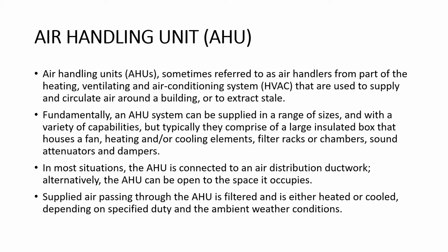So move on to air handling unit, AHU. Air handling units, sometimes referred to as air handlers, form part of the heating, ventilating, and air conditioning system (HVAC) that are usually used to supply and circulate air around a building or to extract stale air. Fundamentally, an AHU system can come in a range of sizes and with a variety of capabilities, but typically they comprise of a large insulated box that houses a fan, heating and or cooling elements, filter racks or chambers, sound attenuators and dampers.